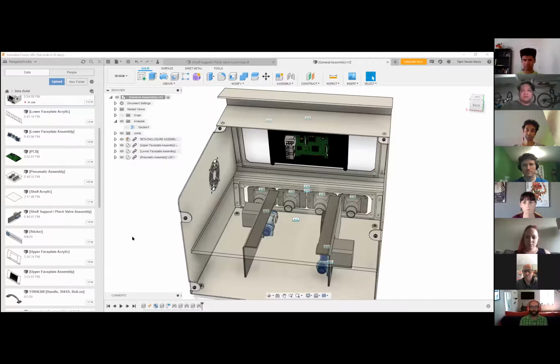30 G should not be too much shock to handle if everything is bolted down and we don't have anything super fragile. I would think the biggest thing is mounting the servo drives. Yeah, if it's in the wrong axis, it could cause them to skip, perhaps. I'm just thinking about the fact that they're the largest, densest piece of mass in there. Yep. And what you're talking about specifically are the motors, right? The big cubic things. Yeah. So it probably makes sense to make sure that those are mounted to the frame, as opposed to being mounted to a flexible piece of plastic and a flexible piece of metal. Yeah, so I'll consider doing that with my design, making sure that it goes straight to the body itself.